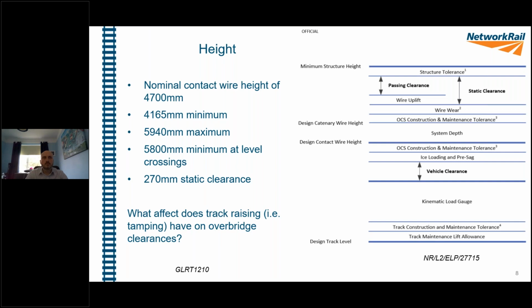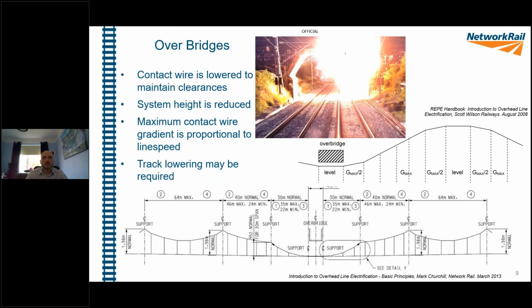If we stick with the theme of bridges, if I can get the next slide. Wiring through overbridges can be very challenging. The railway in the UK was built from the Victorian era, and electrification hasn't necessarily been around since then. There are a couple of techniques that we use to get overhead line through bridges. Ideally, we'd use a free running system. This is where the overbridge is high enough that the overhead line can free run, so the wires can freely run without being attached to the bridge structure itself. This is because the underside of the overbridge is high enough that we have the electrical clearances required.